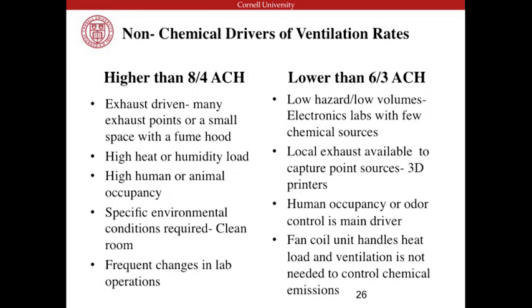The human occupancy or the odor control is the main driver. Some places are labs, but it's an electronics lab, there's no chemistry actually happening in it. And then places where there's a high heat load, like a freezer farm, there's no chemistry happening, it's all the heat. So if we could put in a fan coil unit that takes care of that heat, then we don't need as much ventilation.